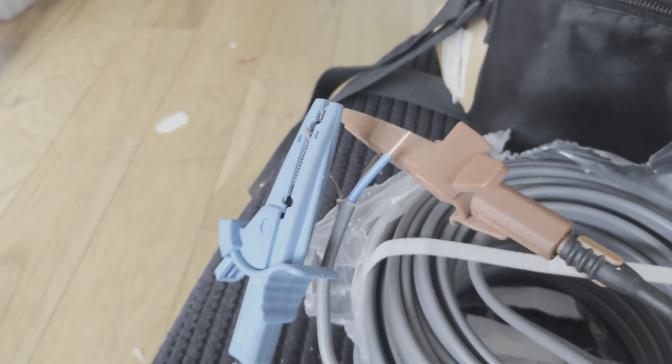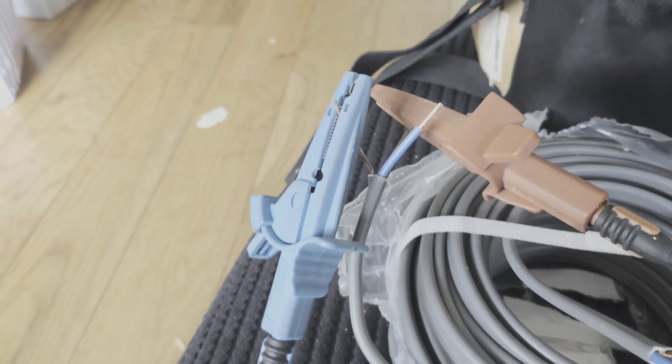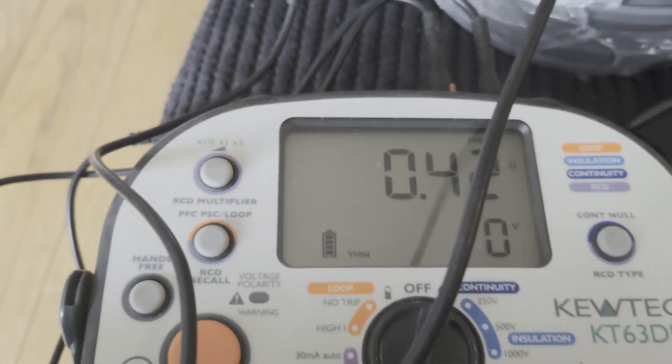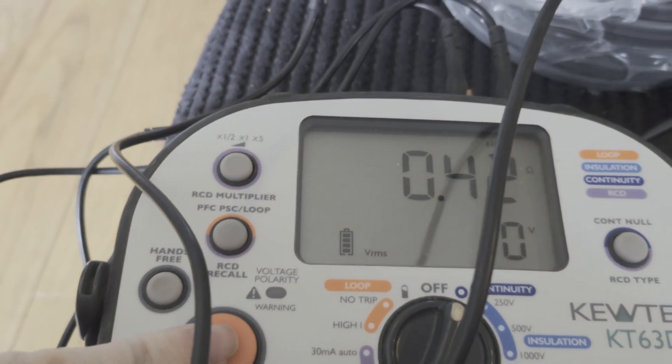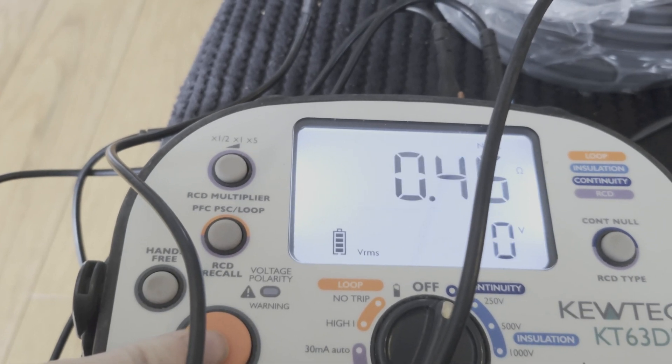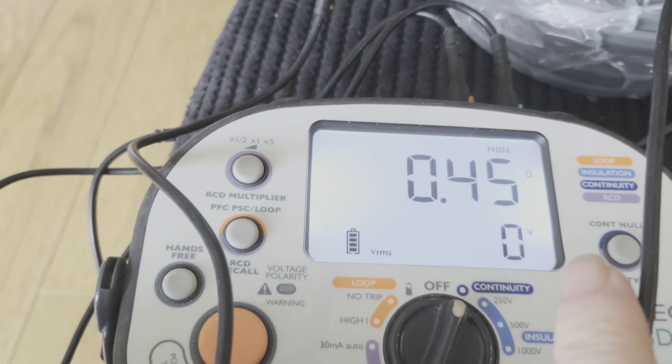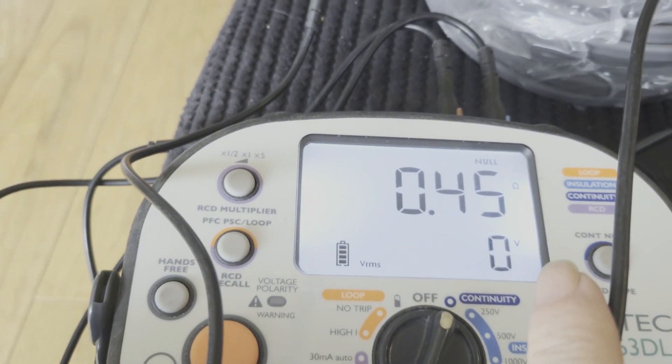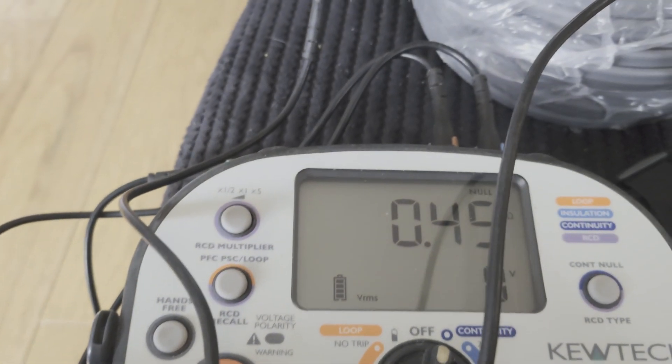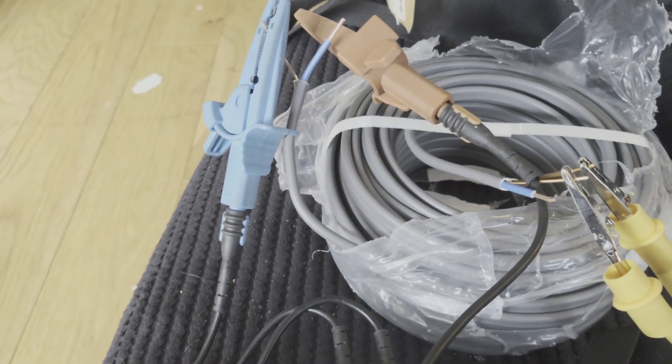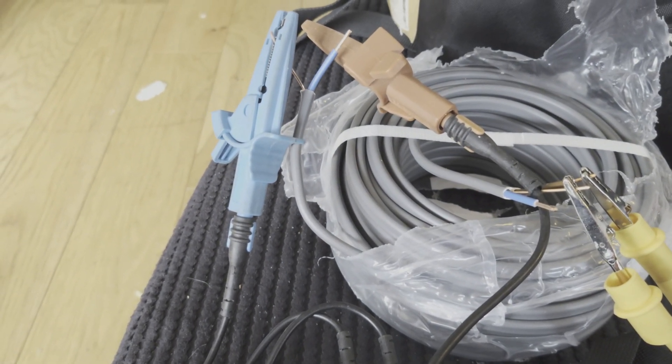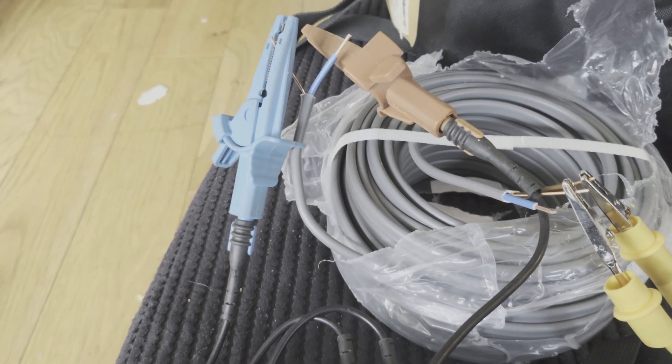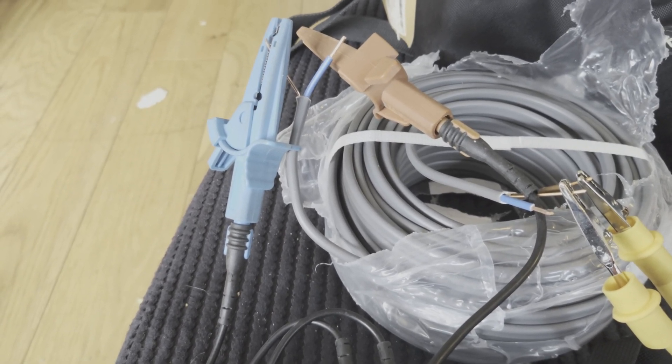There you go. So as you can see, I've got the crocodile clips clipped onto the CPC and the line, so now we're going to take a reading. 0.45. Now how do I know that that's actually right? Well I know that that cable is a coil of about 25 meters of cable, brand new, bought today.